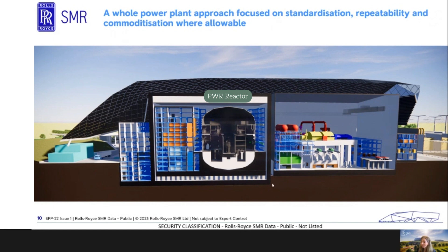We're also using standard fuel. This is the reactor island — the nuclear island — with all of the systems around it. Underneath, you can see a specific feature: the aseismic bearing. The aseismic bearing, which is bespoke to each site, actually isolates the nuclear island and all the nuclear components from the ground conditions. This means that anything we manufacture in the factories can be standardized and shipped to pretty much any site around the world, so we don't need to redesign the plant for specific site conditions — which is a real requirement if you're going to pursue a manufactured approach.